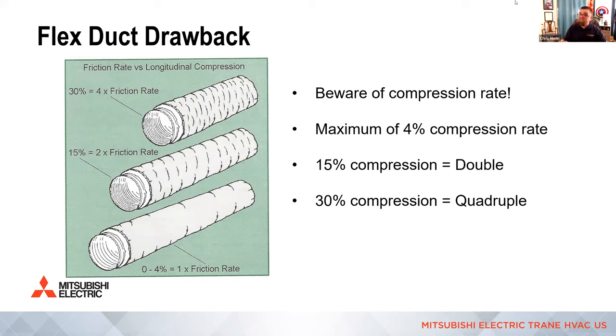But if you install flex duct correctly, it can be used right. Now, I would avoid it when it comes to low static air handlers as much as possible. We want hard duct, straight, large sweeping turns with smooth 90s, if we can. Keep the equivalent length value as low as possible, all right?